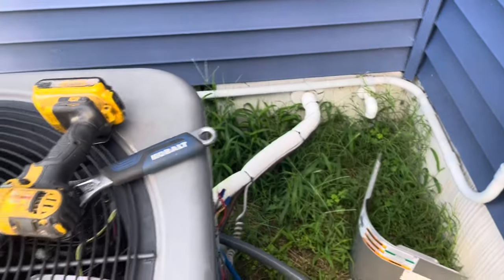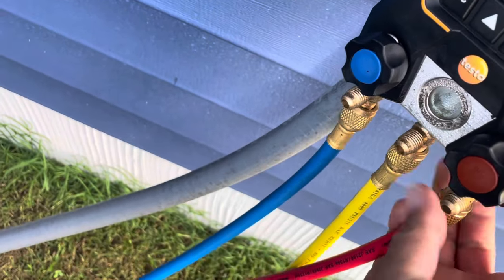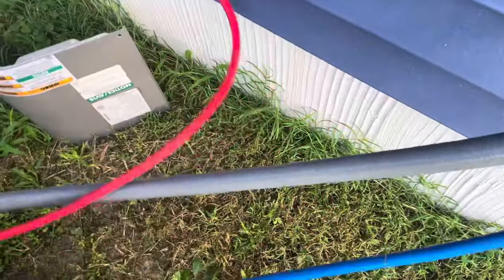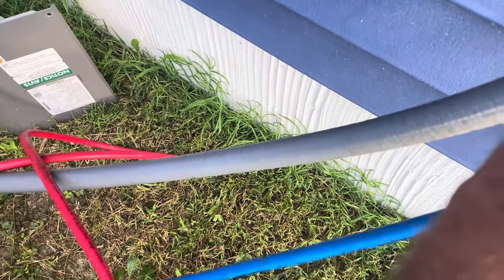All right, we'll let it recover the line set and coil then we'll get busy. Getting close now — we'll go ahead and shut the pump off. We're going to bleed off the rest of this so we're not drawing any air in or pulling ourselves down into a vacuum. There's a little tiny bit left.